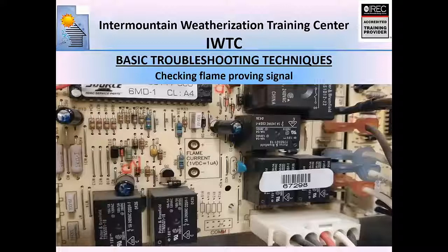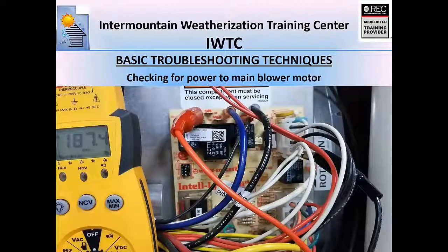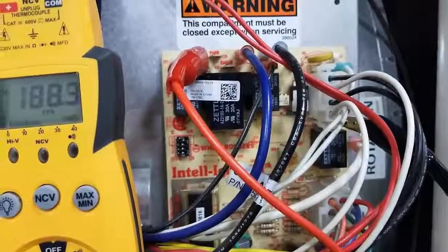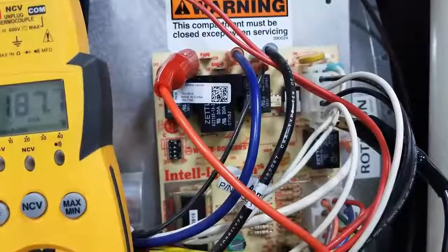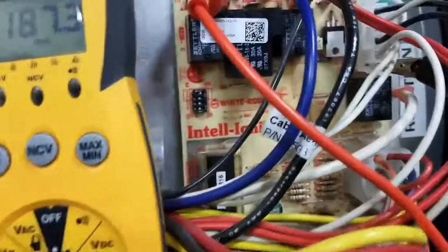All right, we're getting close to the end. So the last part of the sequence is the main blower. I'm going to show you how to check for power to it, and then a simple test for ohming out the windings of a blower motor and checking a blower motor start capacitor. So here we go. Okay, so I've unhooked the wires going to the main blower motor from the circuit board, in particular the heat and common wires, and that's where I've hooked my meter to.